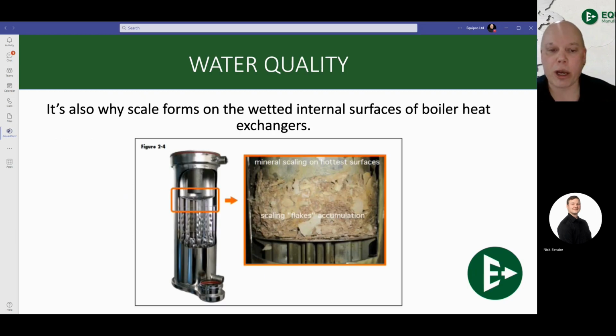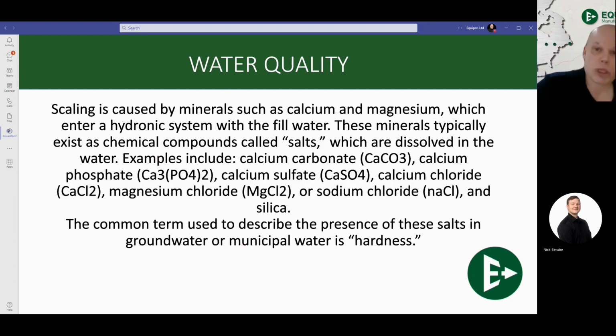It's the hottest area of the system. It's where all of these salts are going to come out of the solution, and it's where the calcium, magnesium is going to flake and accumulate at the bottom of our heat exchangers. It's extremely detrimental to the output of the boiler. It's not going to work as well. You're not going to flow as well, and it's also not a warranty situation. So you need to treat that water first to make sure that we get the mineral salts out of there, or not let them go in the first place.